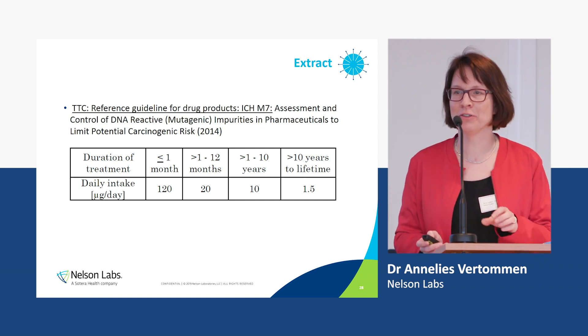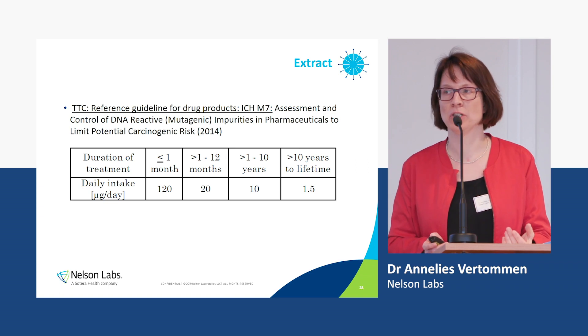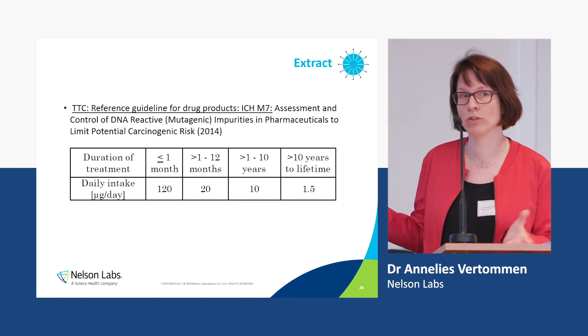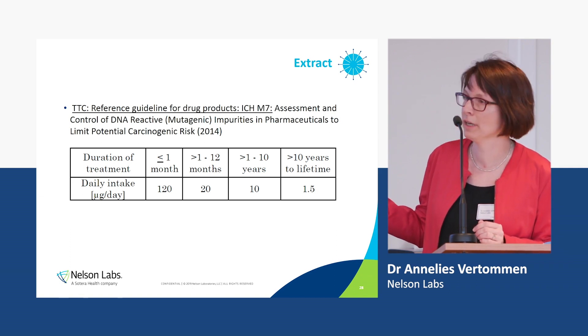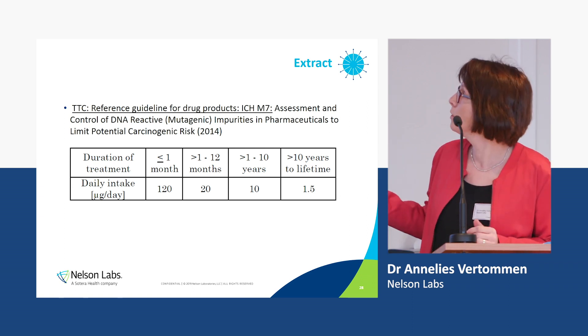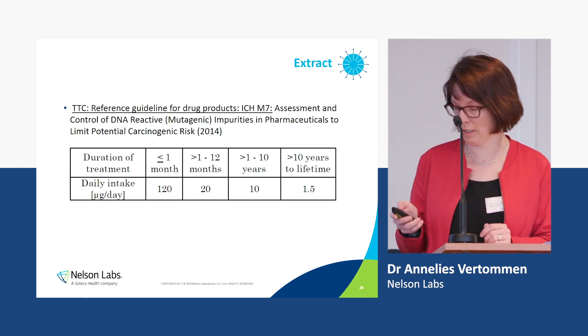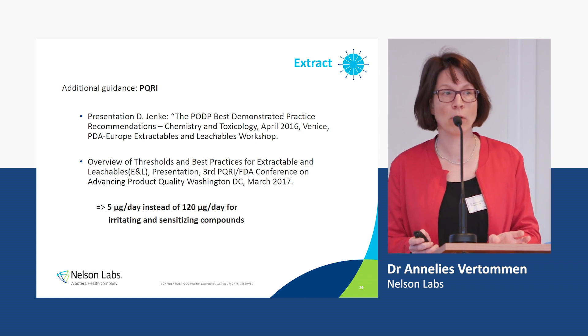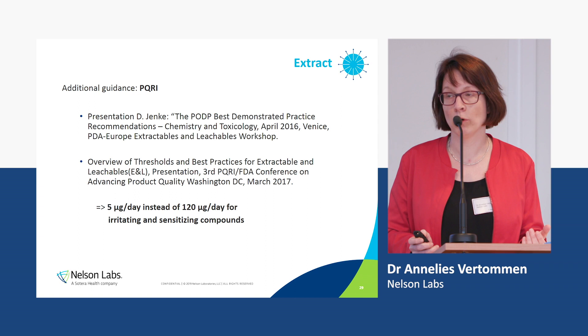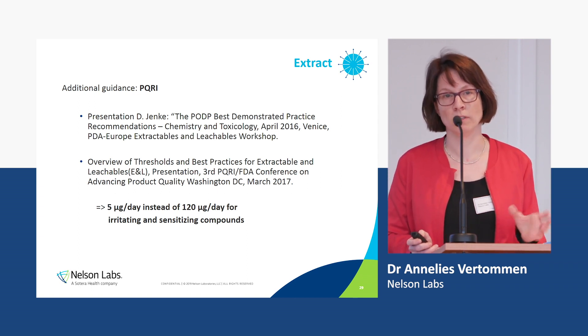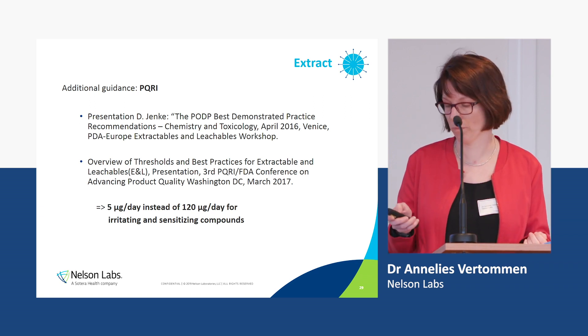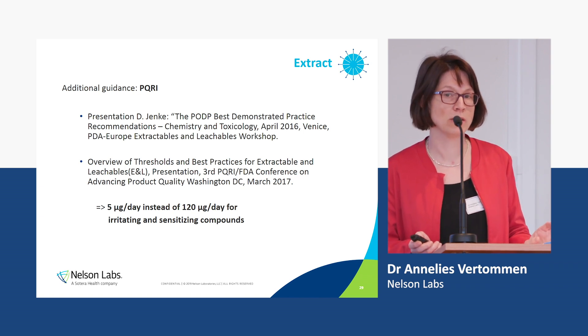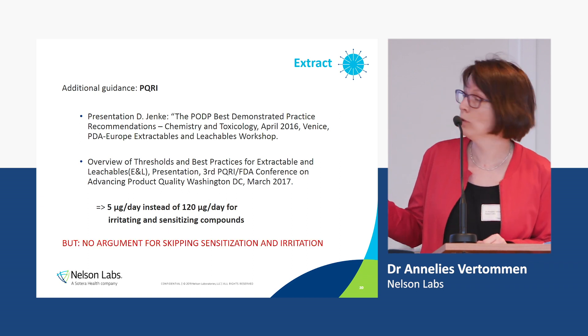For the threshold, you need to look at the daily dose the patient is getting. For medical devices, the most important ones — due to categorization of medical devices — are 120 micrograms per day for devices with a time of contact less than 30 days, or 1.5 micrograms per day for long-term contacting devices. As we know from the pharma world, it's advised to use 5 micrograms per day because this is the threshold for irritation and sensitization.